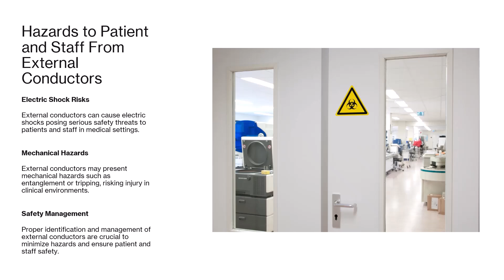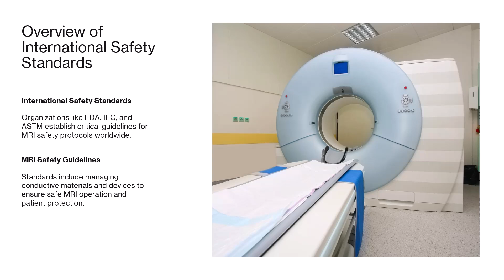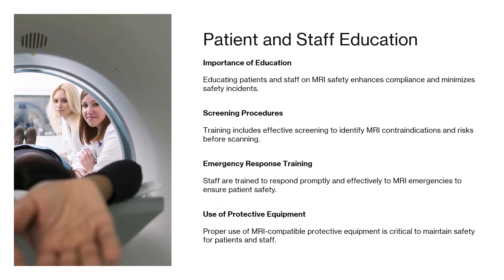Standards from organizations such as the FDA, IEC, and ASTM provide guidelines on MRI safety, including managing conductive materials and devices within the MRI environment. MRI centers must develop and enforce institutional policies based on applicable regulations to ensure consistent and compliant management of external conductors. Training staff about MRI risks and safety procedures improves compliance and reduces incidents. Training should cover screening, emergency response, and proper use of protective equipment, as well as the safety zones.